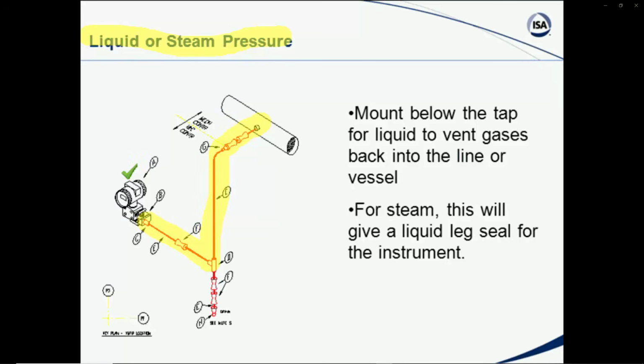It does have a liquid leg there that will have to be taken into account if it's significant with the range of the transmitter. For instance, if that leg is only a couple of feet and this is in an 800-pound service, it's going to be insignificant. However, if that leg is, say, 4 or 5 feet of liquid, then you'd have to maybe take that into account if the process variable was only 50 psig or something along that line. So that would be a case of your elevation suppression, and you'd have to take that into account as you calibrated that particular device.